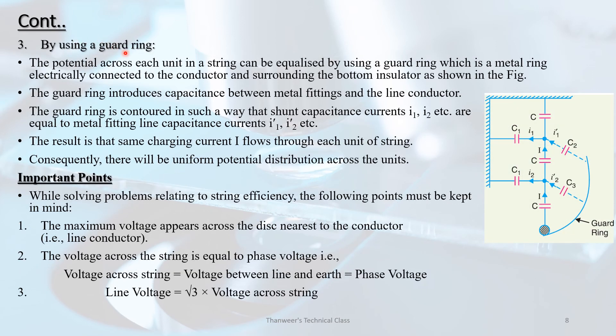By using guard rings: A guard ring is a metal ring electrically connected to the conductor and surrounding the bottom insulator. The guard ring is arranged such that the shunt capacitance currents i1 and i2 are equalized by the line capacitance currents from the guard ring, so that the same charging current flows through each disk unit.